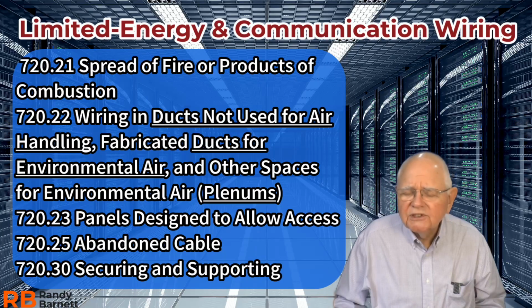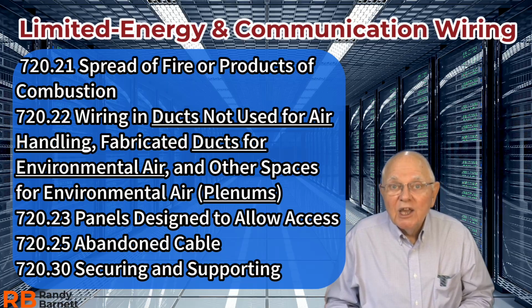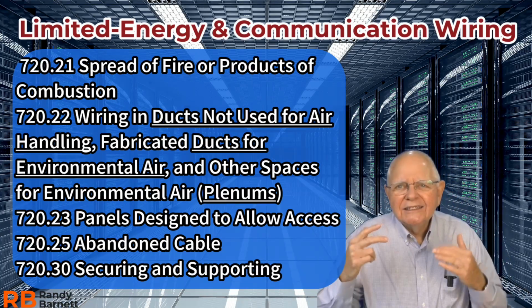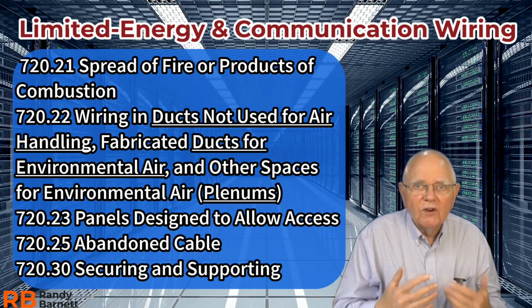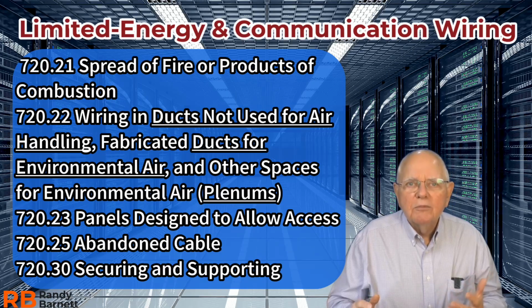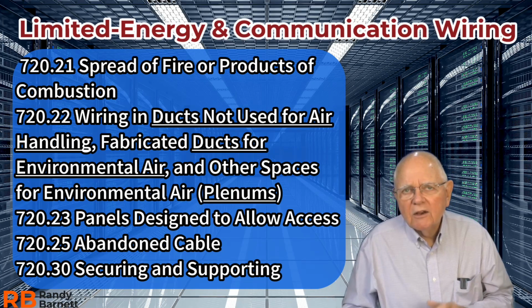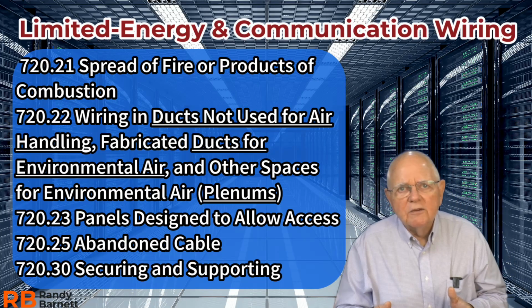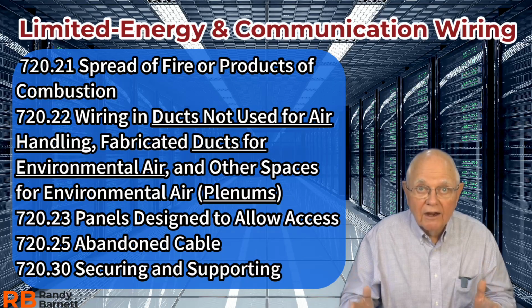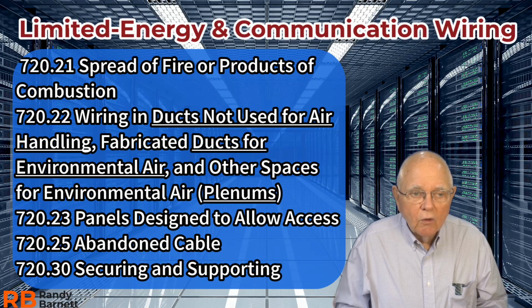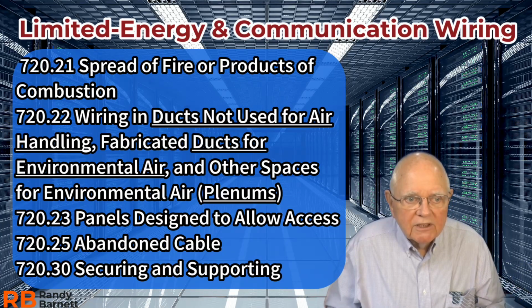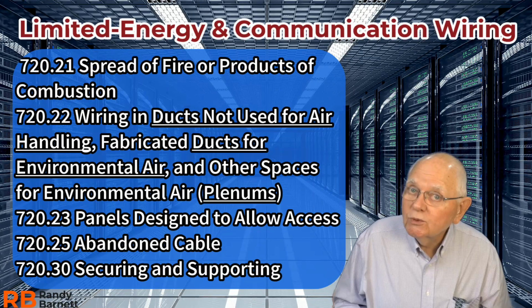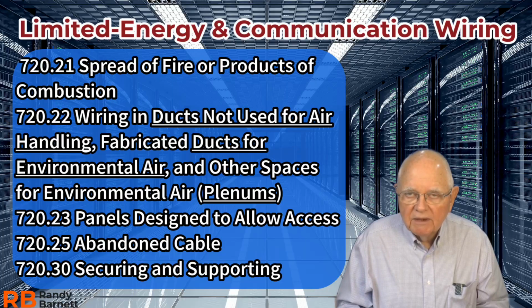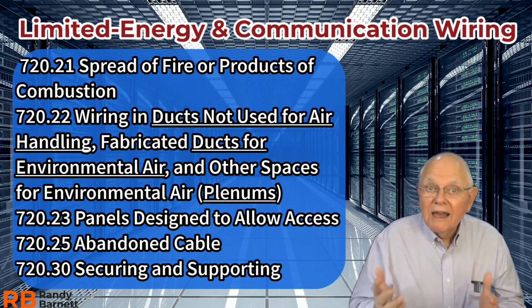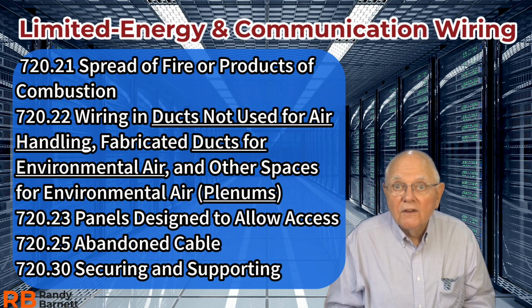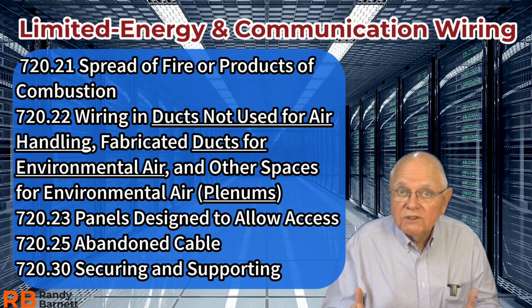720.22. It's a mouthful just to say the title. Then we'll break it down and talk about it. But 720.22 says wiring in ducts not used for air handling, fabricated ducts for environmental air, and other spaces for environmental air, plenums. What we're really talking about here, very similar to what's in Article 300, we have three spaces that we're talking about. We have wiring ducts that are not used for air handling. That's number one. So what would that be? A duct that maybe transports dust. And if you think about it, probably the big issue with dust, I don't want fire and explosion caused by some electrical fault inside of that duct. So we're not allowed to use even limited energy cables inside of those ducts that are not used for air handling, used for something else.